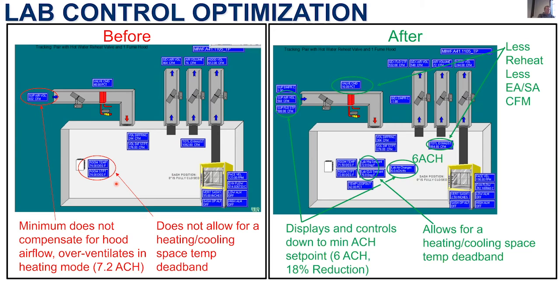So in this example, there's two opportunities here. The lab controller does not allow for a deadband on space temperature because they're like, oh, it's a lab, it's got to be really precise. But not all labs are created equal. So I have to basically break this controller to give it a space temperature deadband, because let's be honest, we're sipping and smelling wine here. I don't really care if it's 74 or 75, right? If I'm holding that precise of control, I'm definitely doing a lot of simultaneous heating and cooling.